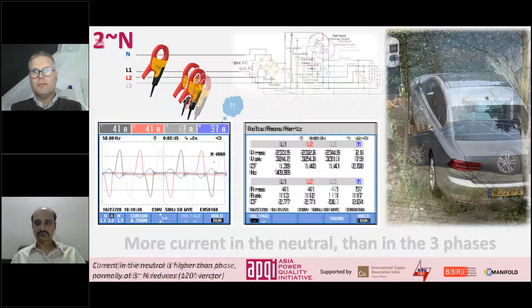That's terrible for the system, because when we do a cable calculation or a cabinet calculation, normally in the 50 hertz period, we would halve the neutral. For example, the phase is 70 millimeters and the neutral is 35 millimeters. But what you see here is phase 1 is 41 amps, phase 2 41 amps, phase 3 41 amps, and the neutral is 71 amps. How is that possible? That's possible because of the third harmonic, and that's killing cables, killing cabinets, and heating up connectors. So this 71 amps is a problem.